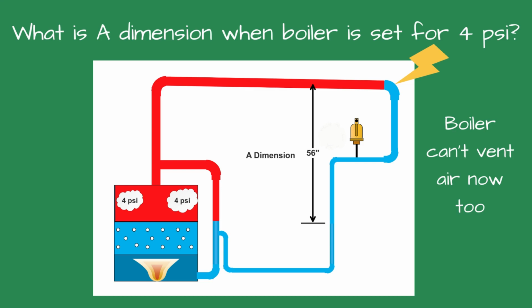Imagine a pipe in the basement is not that tall. If this is the case, the water column will rise up until it goes into the horizontal steam pipe. Steam and water do not play well. You would have banging the likes of a Blue Man concert and a very unhappy customer. Not only is it noisy, but it's dangerous and could damage fittings and components.